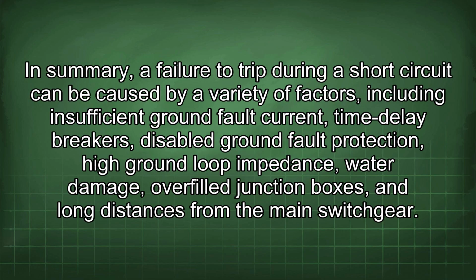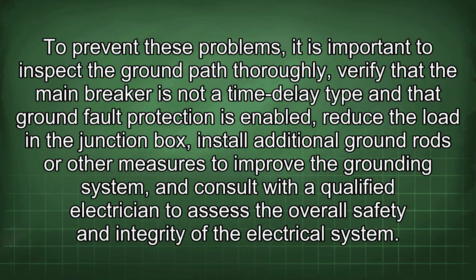In summary, a failure to trip during a short circuit can be caused by a variety of factors, including insufficient ground fault current, time delay breakers, disabled ground fault protection, high ground loop impedance, water damage, overfilled junction boxes, and long distances from the main switchgear. To prevent these problems, it is important to inspect the ground path thoroughly, verify that the main breaker is not a time delayed type and that ground fault protection is enabled, reduce the load in the junction box, install additional ground rods or other measures to improve the grounding system, and consult with a qualified electrician to assess the overall safety and integrity of the electrical system.